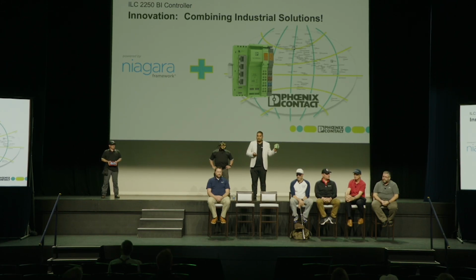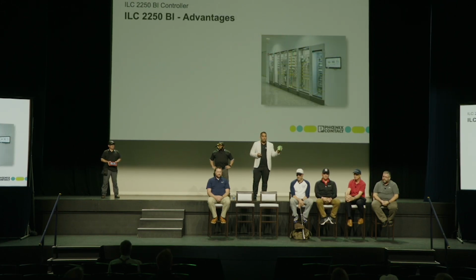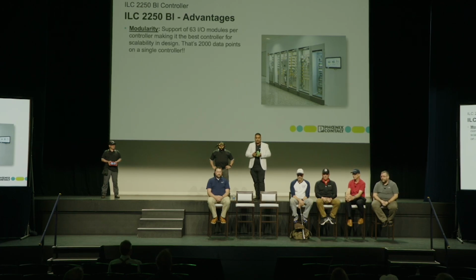What are the benefits for your projects? Let me go through some of the key advantages. It's modular. These are the I/O modules that connect directly onto the ILC controller. I know you can't see it as much, but it's really small. The idea is that 63 I/O modules can be connected on one single controller. So what does that mean for your projects? You can connect around 2,000 data points on one single controller. It's a very versatile, modular controller.